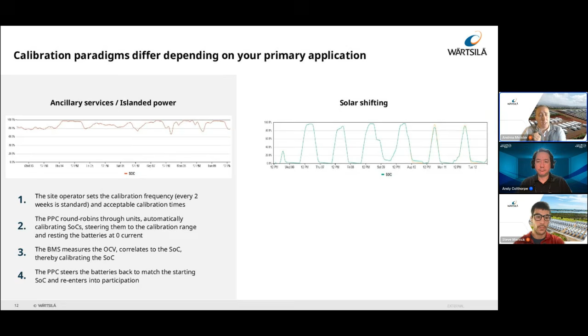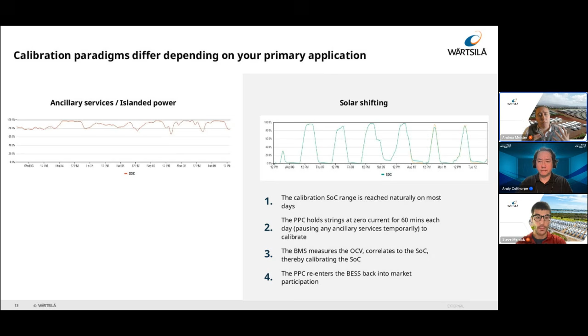At a solar shifting site, we see a somewhat different role for those components than might be expected. For example, we see a lot of charge during the daytime and discharge in the evening, and that battery is being cycled from perhaps 100% to nearly 0% state of charge every day. This allows for some natural calibrations to happen. During that, the PPC's primary role is to hold those strings at zero current during those very low states of charge at night, pausing any ancillary services that might have stacked operations to perform calibration, and then re-entering those strings into the market.